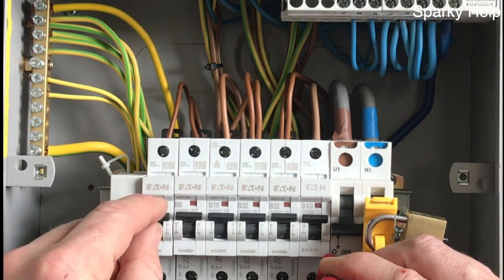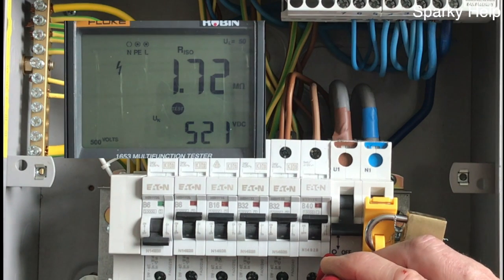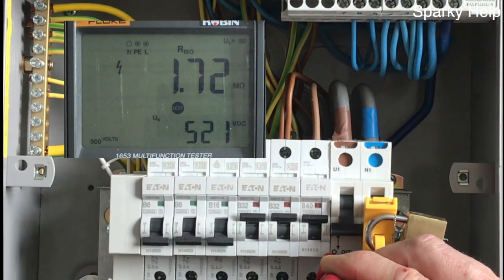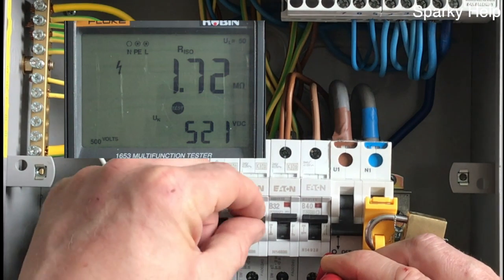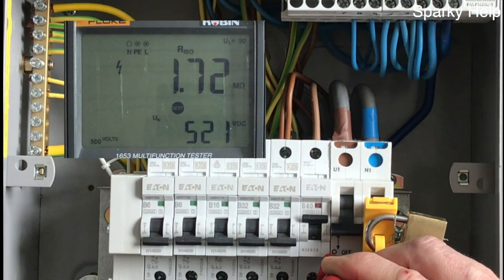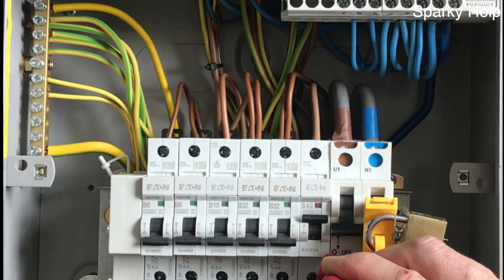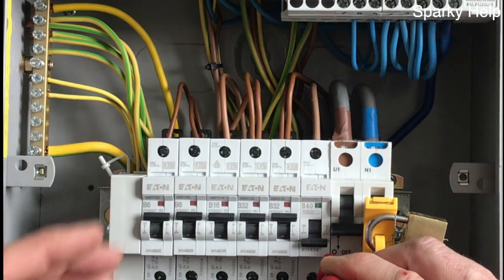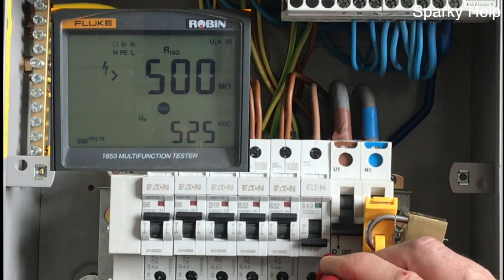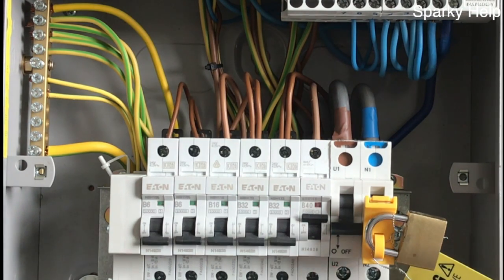And I can press the test button. And it's going to be the last one, isn't it? And that's the one with the fault on. But we can just prove to make sure. Let's just check. So these all should be clear. So we now know the fault is in the circuit number 1, which was the shower.